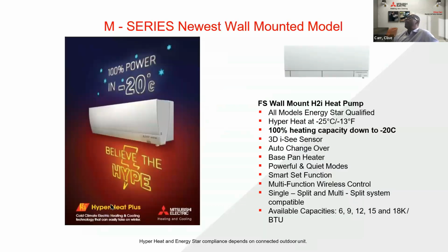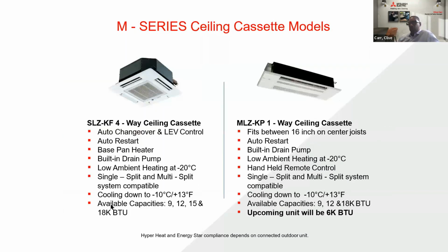We've seen improvement in our product offering. I'm not going to go into great detail on the features, but just to say that we're continuing to improve our product line, where on our single zone wall mounted model, you can achieve 100% heating capacity down to minus 20. And then it operates down to minus 30, where the capacity starts to taper off. So when you get down to minus 25, you may end up with approximately 90, 92% of your available heating capacity, still quite a bit. So you can really size the heat pump to serve as a primary and only heating system.